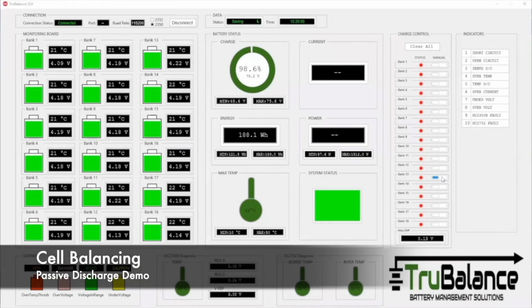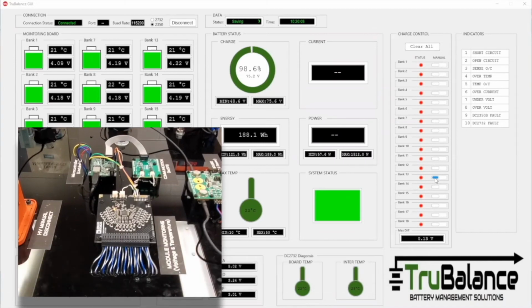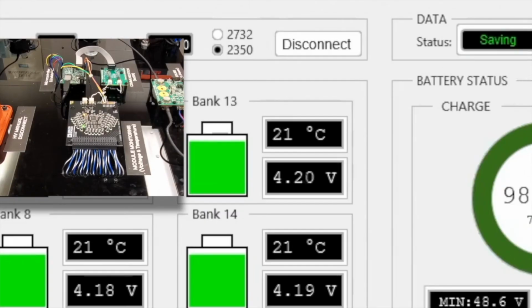Cell discharging is directly controllable through our GUI. When charging mode is initiated, our system will automatically detect an out-of-balance condition, then charging will pause and balancing will initiate. In this demo, we are showing a manual control of the discharging feature through a clickable button in our GUI. Here we can see cell number 13 as it's discharging. You can clearly note the voltage reduction of cell number 13 compared to other cells.